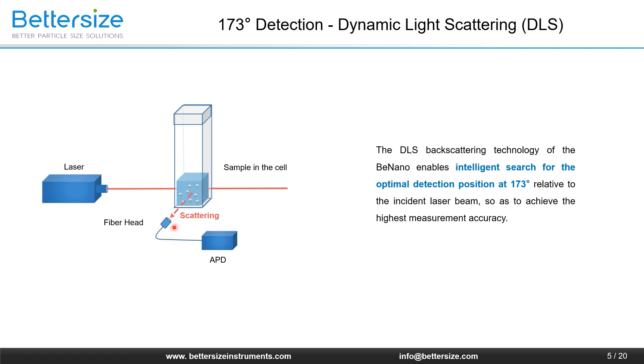Traditionally, the 90-degree detection is used in DLS analyzers. Now, an advanced optics 173-degree detection is utilized, and this novel design allows intelligent search for the optimal detection position. By moving the lens, the detection point can be set at any position from the center to the edge of the sample cell. This allows the detection of different types and concentrations of samples. The optimal detection position and laser intensity are determined intelligently for each specific sample according to its concentration, size, and scattering ability, achieving the highest measurement accuracy.